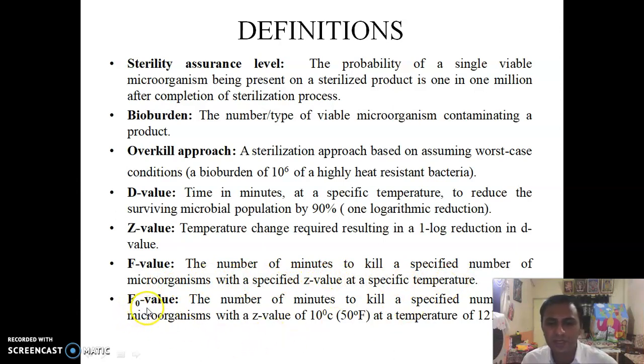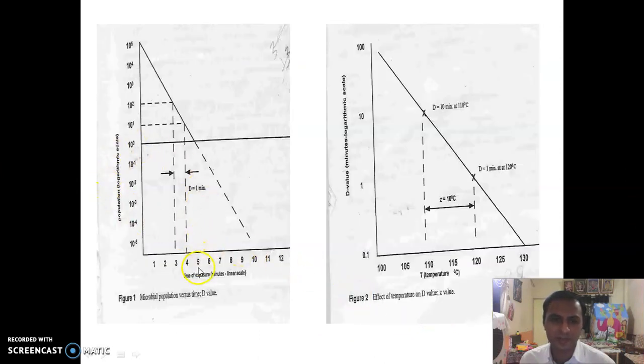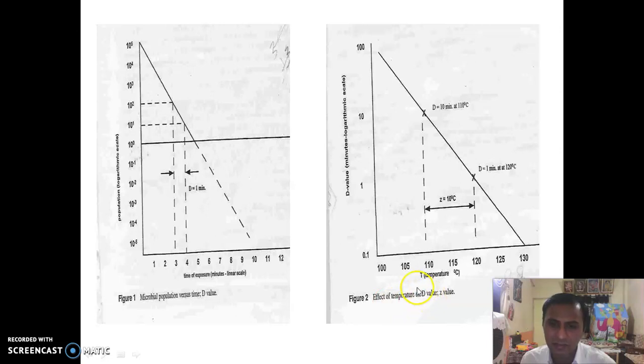The F₀ value is the number of minutes to kill a specified number of microorganisms with a Z-value of 10 degrees Celsius at 121 degrees Celsius. Looking at the graphs: the first graph shows D-value, with time of exposure in minutes on the x-axis and population on the y-axis. The second graph shows the effect of temperature on D-value and Z-value.